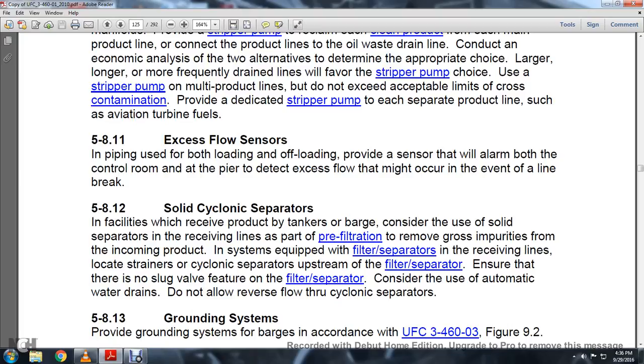5811 excess flow sensors. In piping used for both loading and offloading, provide a sensor with an alarm to the control room when excessive flow is detected that might occur in the event of a line break. 5812 solid cyclonic separators. The facility receives product from tanker barges. Consider the use of solid separators in receiving lines as part of pre-filtration to remove gross impurities from the incoming product.